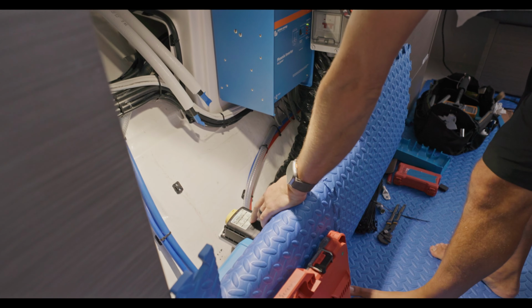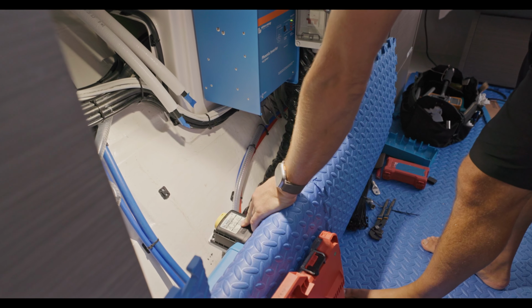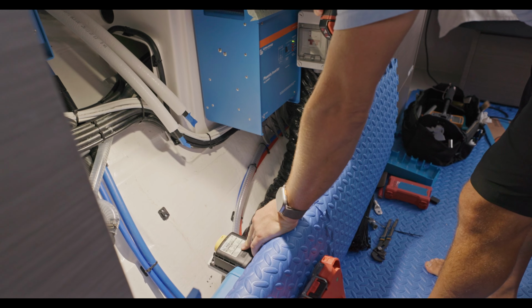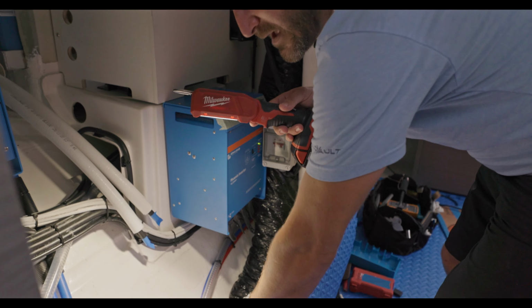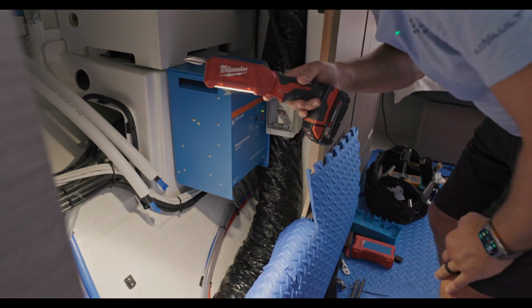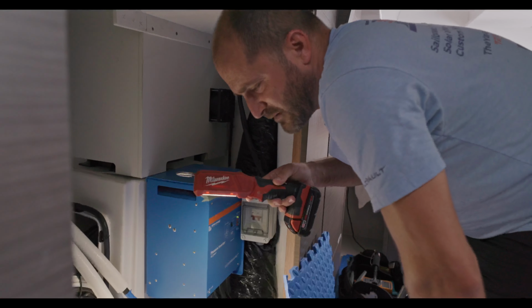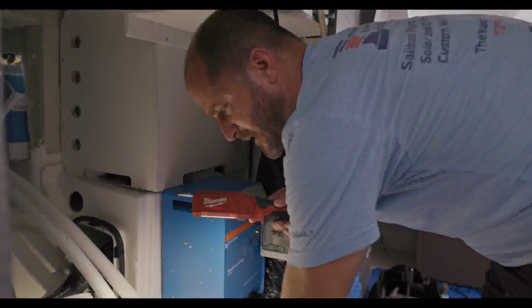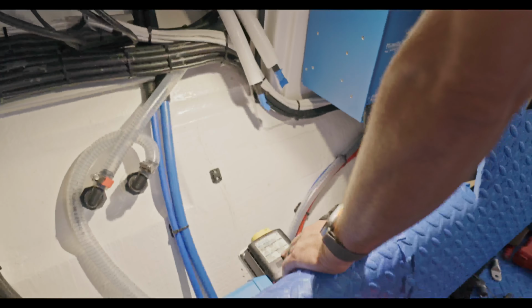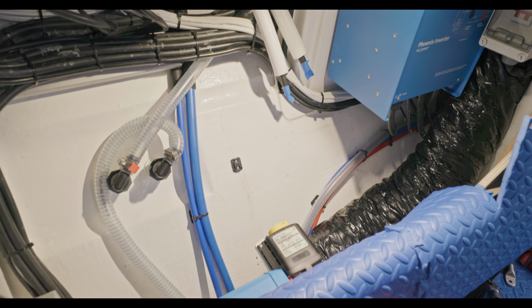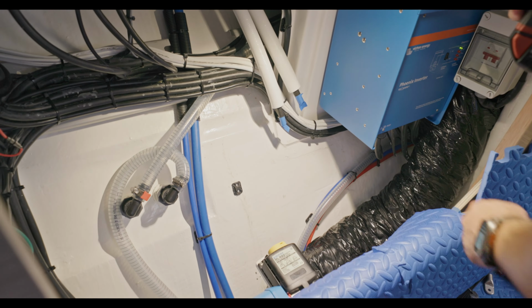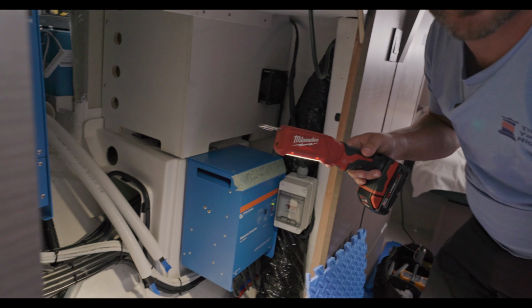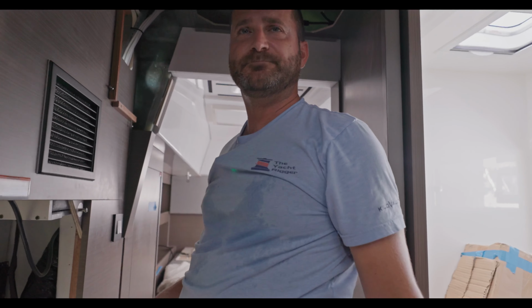This switch right here is a switch to turn off the inverter. It's really nice, and a recommendation by ABYC, to have a means of shutting off the DC power to an inverter if you need to service it. It's also nice to be able to do resets and things like that. So here's the remote battery switch for one of the inverters, and there's going to be another one for the 230 volt inverter. And then we have two distributors remotely mounted here for our 48 volt power distribution.